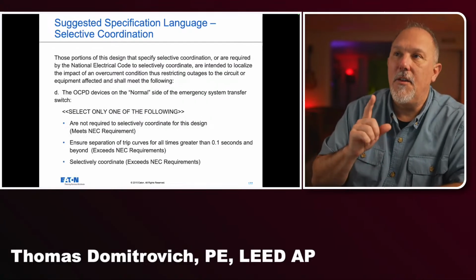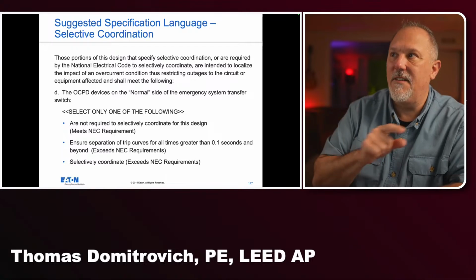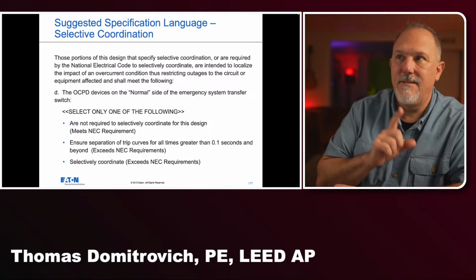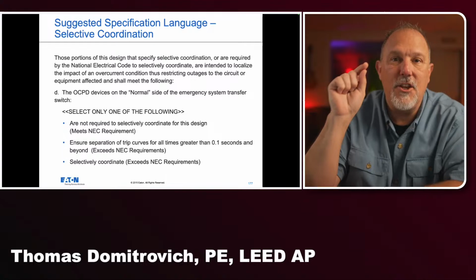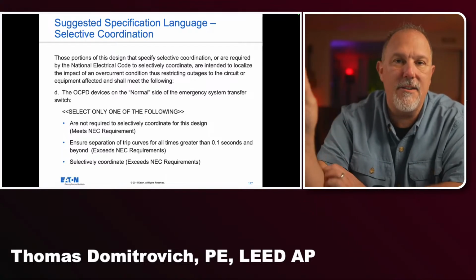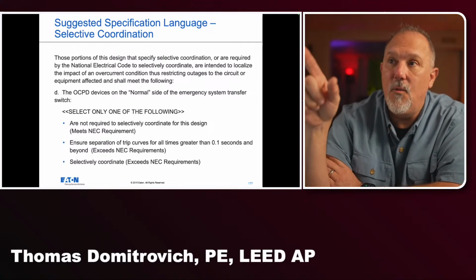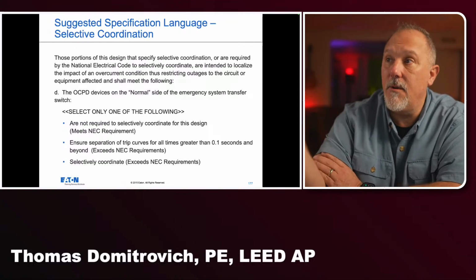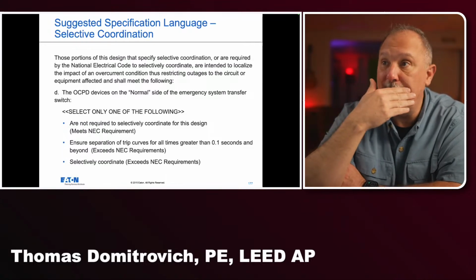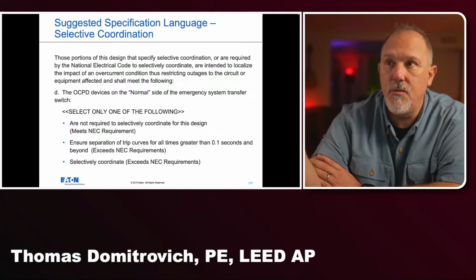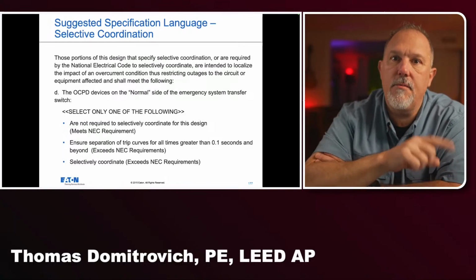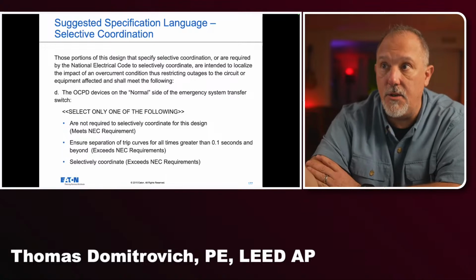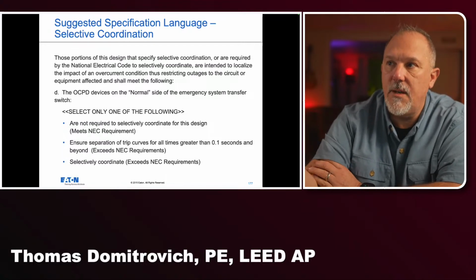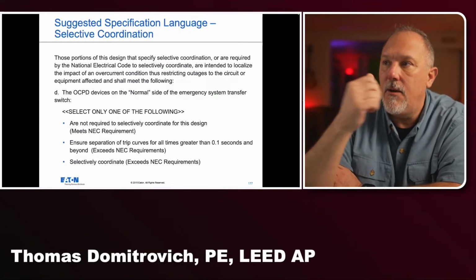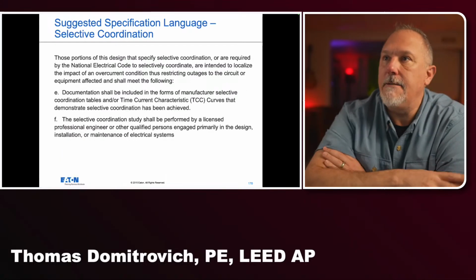D. The OCPD devices on the normal side of the emergency system transfer switch, and you would make the engineer decide what we are going to specify. They're not required to selectively coordinate, and it meets the NEC requirement, which would be true as of before the 2023, because 2023 now mandates those to selectively coordinate. Ensure separation of trip curves for all times greater than 0.1 seconds. You could do 0.1 seconds, or you could selectively coordinate.